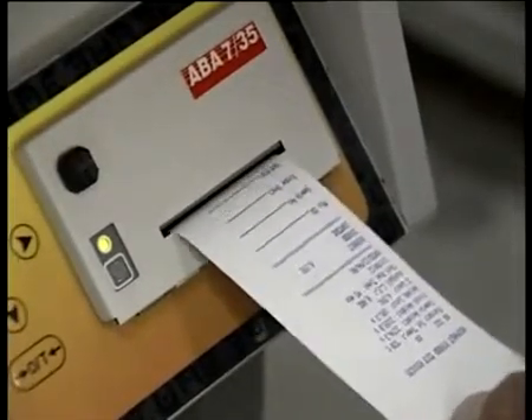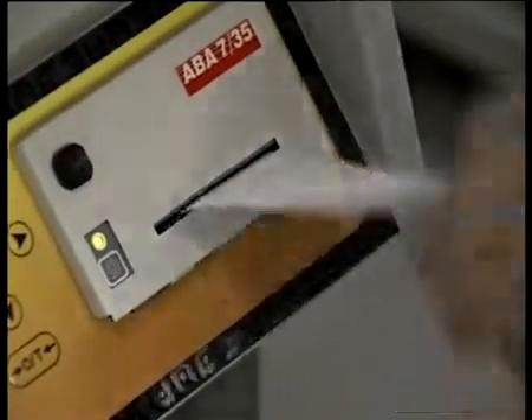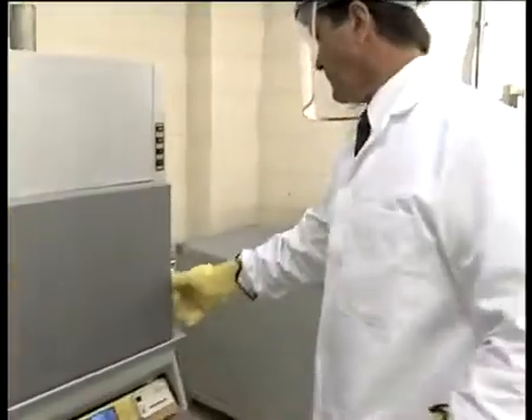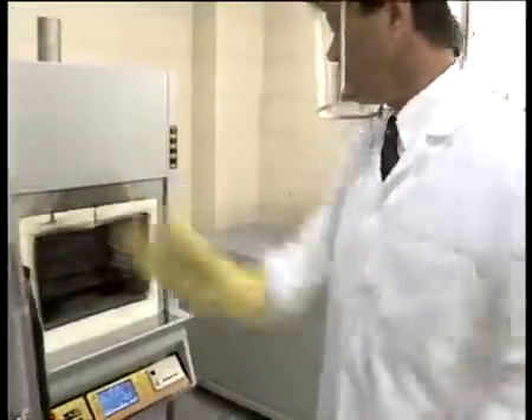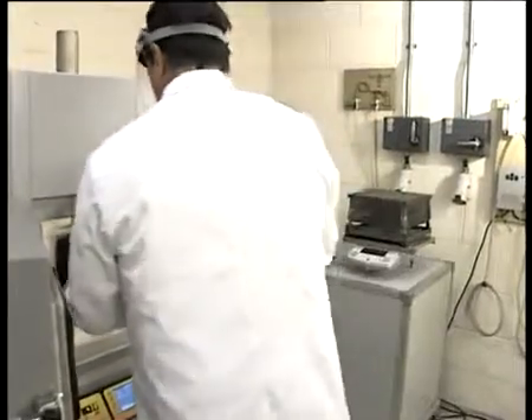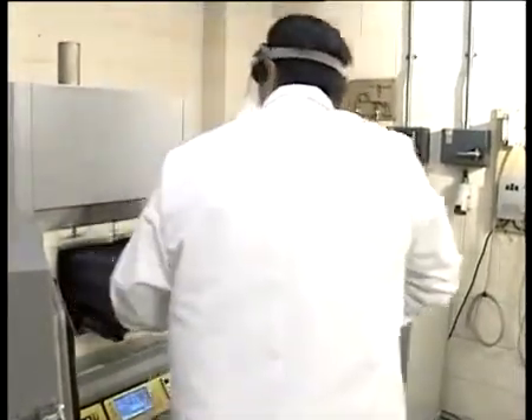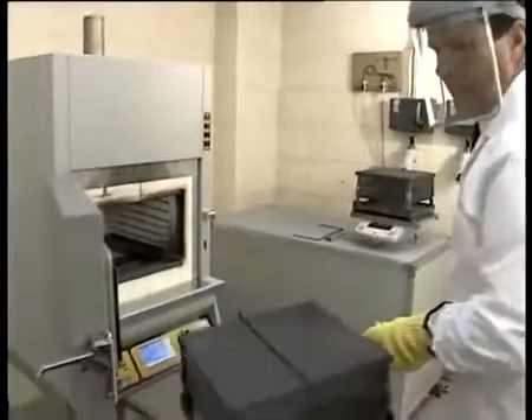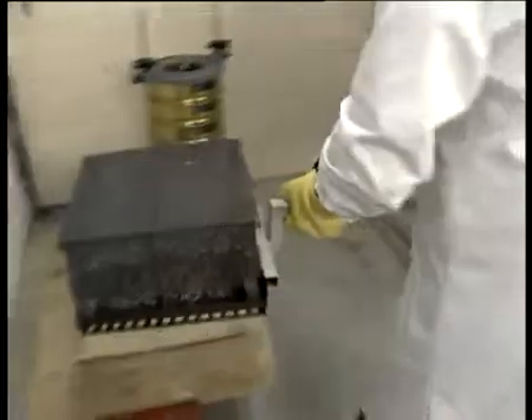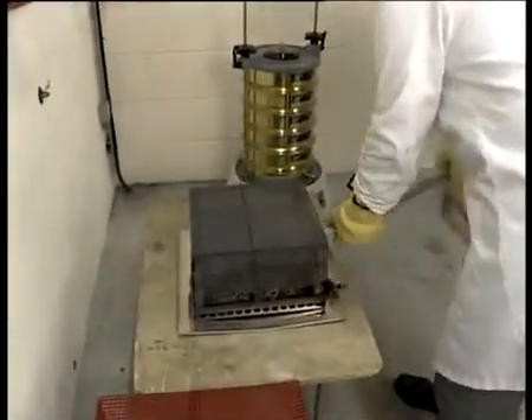Calibration is only required on the balance in the furnace, as opposed to the wide variety of equipment used in the traditional method. With Carbolite's loss on ignition test, the samples are weighed on an external balance. The balance pan extension has been designed to simplify sample loading and unloading and also to protect the heating elements.